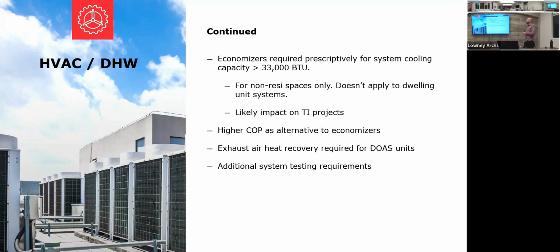Another example is multifamily residential buildings. This requirement doesn't apply to dwelling units like apartments in the building, but for the common areas in large multifamily buildings, like lounges and similar areas, you would put a split heat pump or a VRF system serving those areas, and you would be fine. Now, if that system is about 3 tons capacity, you have to provide either a dedicated outdoor air system again, or you have to have a super high COP, which is the efficiency of the system. So a super high efficiency system if you don't provide any economizer or dedicated outdoor air supply to those zones.